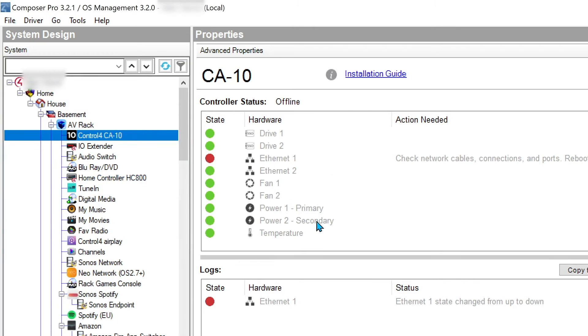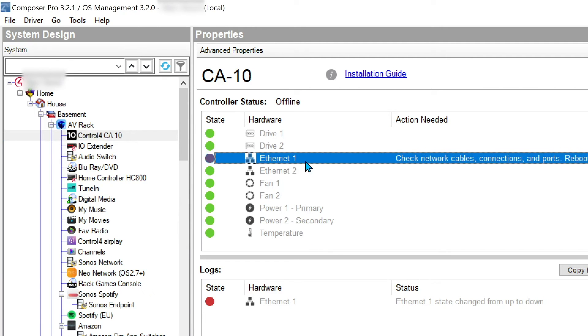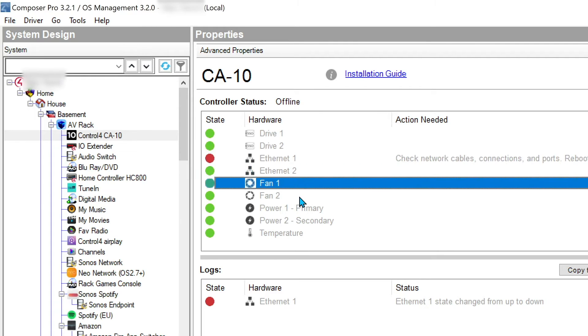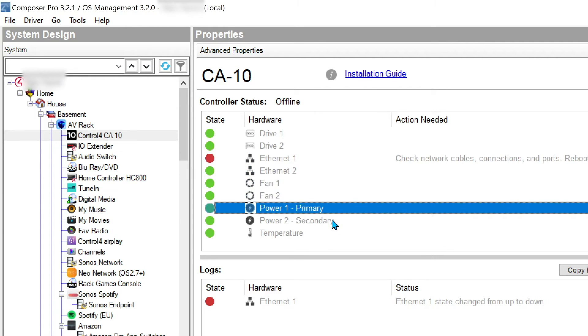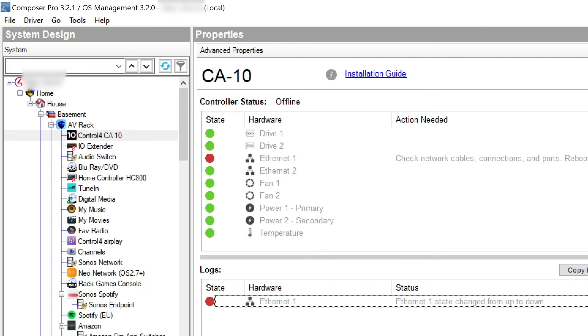Right. So now the CA10 has added itself into the project. It's going to bring that up there. We can see we've got one of the Ethernet cables online. We'll put the other one in once we've got it updated. And we can see the status of drive one, drive two are online. Ethernet one is offline, but that's fine. Ethernet two is online. Two fan circuits are online and the two power circuits are online. And we've got temperature. Again, we have the logs and warnings here. So we have complete logs on this processor.